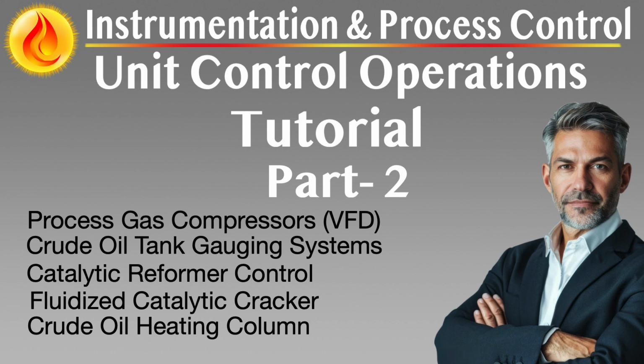Independent high-level alarms, IHLA, and safety integrity level rated logic controllers provide automatic tank isolation or pump trip commands upon detection of critical thresholds. These systems are often decoupled from the primary gauging sensors to ensure independence and redundancy, and they must comply with international standards like API 2350 or IEC 61511. Some tanks also include radar-based overfill detection sensors mounted at discrete elevations to provide rapid response level detection regardless of tank geometry or turbulence. Data integration with enterprise platforms has expanded the value of tank gauging beyond physical measurement.